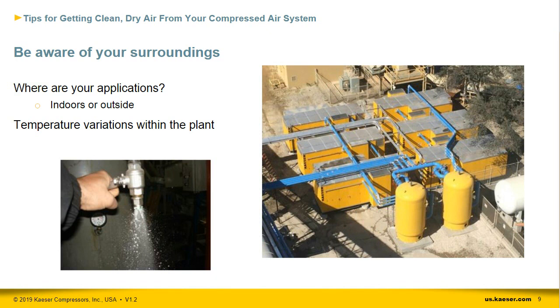Your compressor is going to be a very effective heater. 96% of the energy that goes in can be recovered as usable heat. But if you're not moving the heat out of the room, then that's going to build up over time, and you're most likely going to have a shutdown of your equipment. So if there are wide temperature ranges within the plant, that's something else you want to look at as well.